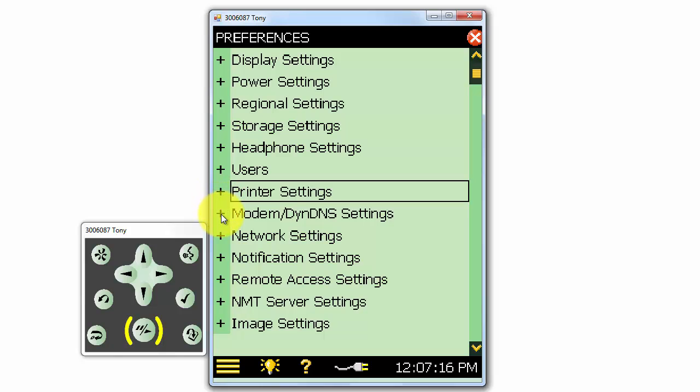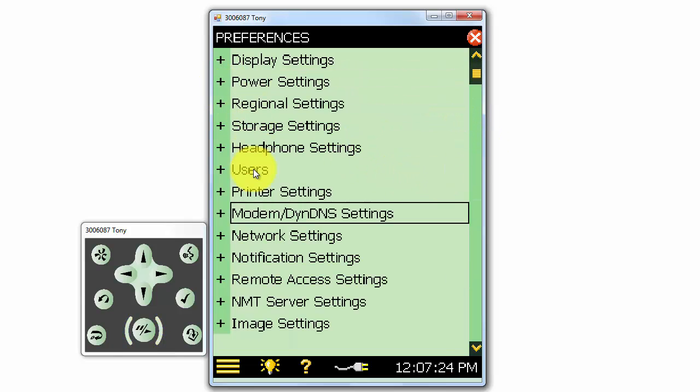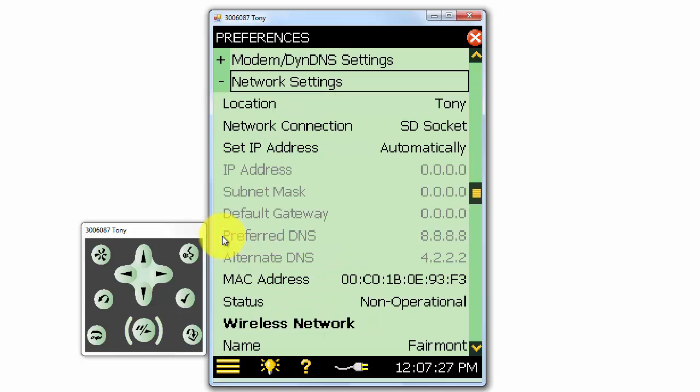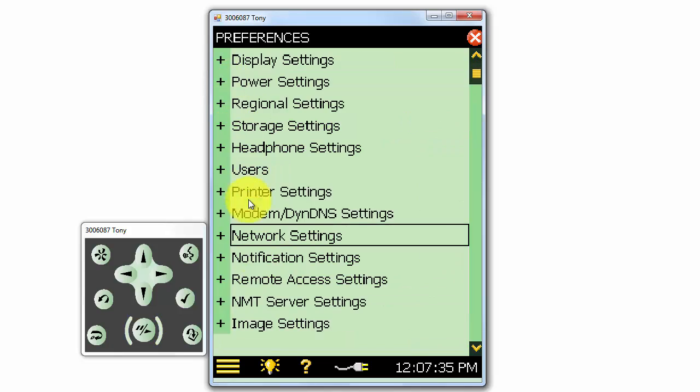We can set up the meter to connect to a modem or ethernet network, so we can access it remotely. Under network settings, we can configure the meter to be used on the network. I have a wireless SD card in my meter, so I could use that as the network connection. We could also connect directly to the ethernet port on the bottom of the meter.